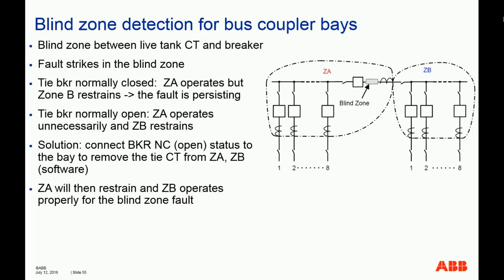So the solution that we mentioned before is to connect the status or any type of logic to indicate that the breaker is open now, so remove those two CTs from the differential zone operating algorithm, the differential calculation, so that once you remove that CT, zone B will operate and zone A will restrain. So that you will not cause unnecessary operation in zone A and can speed up operation of zone B.